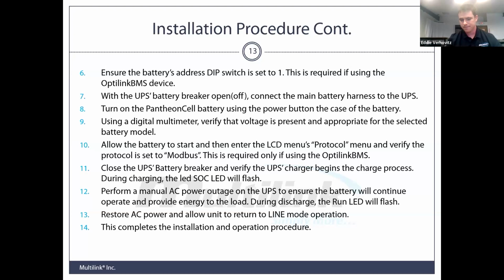flowing into the battery. At this stage, step 12, we want to perform a manual AC power outage to ensure that the battery will continue to operate and provide energy to the load. So during this time, we'll actually disconnect incoming AC power. You can do so with an AC breaker or pulling a line cord. During this time of discharge, the run LED that is displayed on the Pantheon battery will flash.